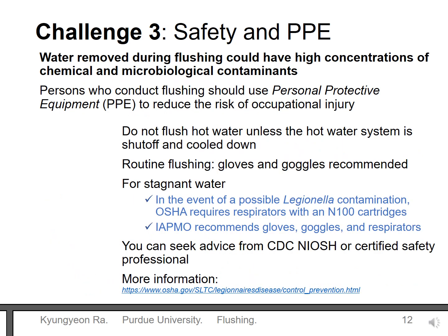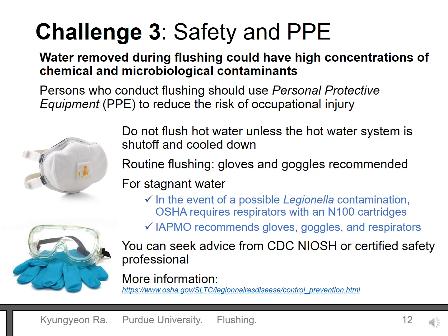Another challenge with flushing concerns workers. Different levels of personal protective equipment are needed depending on what is in, or what could be in, the water. Scalding is a real concern for hot water. Some buildings have very hot water and hot water recirculation systems, so do not flush hot water directly. Typically these systems are shut off and then cooled, and after cooling these systems should be flushed with cold water. If the cold or hot water contains high concentrations of chemical and microbiological contaminants, persons who conduct the flush should wear safety gear such as gloves, goggles, and consider a mask. N95 masks were approved by NIOSH, but when harmful organisms like Legionella are suspected to be present, OSHA requires wearing N100 respirators with cartridges.